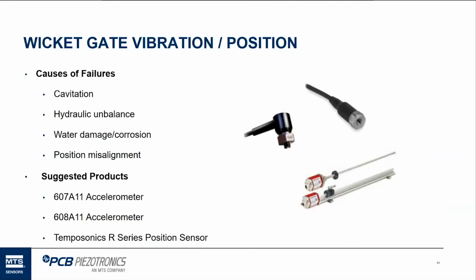We have our position sensors that can look at the actual position of the wicket gate and look at the misalignment of the position. That's through our sister company, TEMPOSONICS. But we're capable of providing that. And we have a couple sensors that are great to look at wicket gates because they're underwater. Our 607 and 608 series accelerometers can look for cavitation and look at imbalance problems and so on underwater to see these issues.